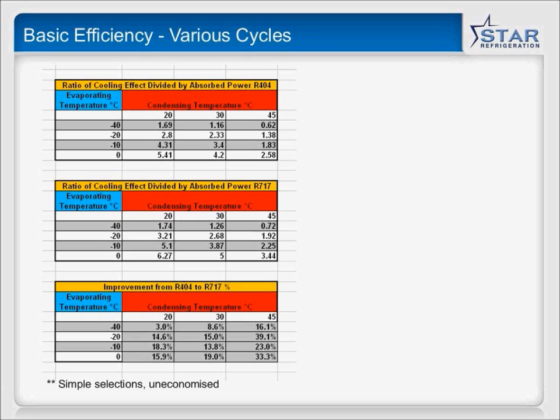Likewise, though, so if we could change from condensing at 30 degrees, so this is the condensing pressure I was talking about, by dropping that down by 10 degrees, we can get a 28% improvement in the performance of the plant. Now, clearly on a warm day, the condensing pressure is still going to be relatively high, but what about winter days or fairly cool days? We've got a fairly cool climate in this country. It doesn't get terribly warm all the time. What if we can get the head pressure, the condensing pressure down?